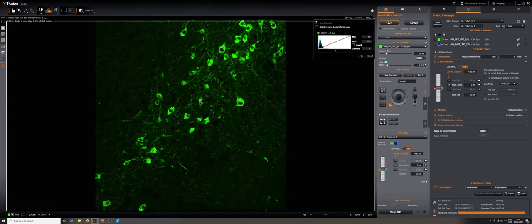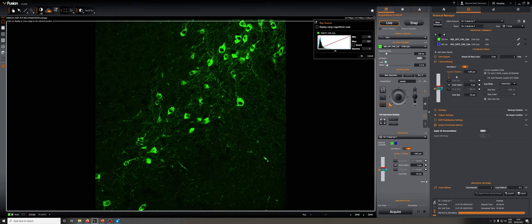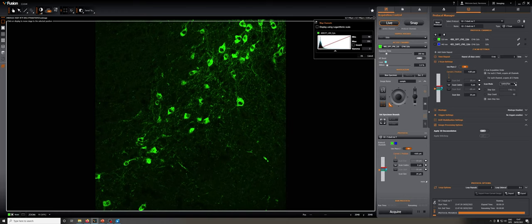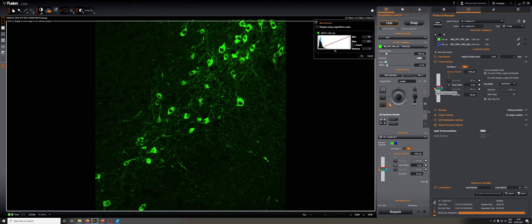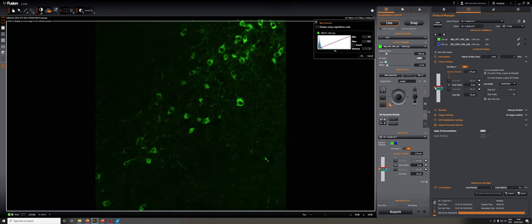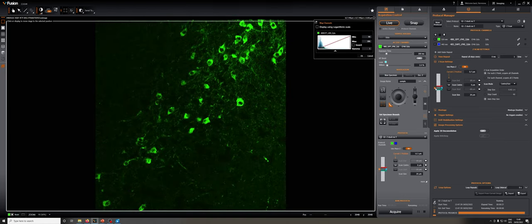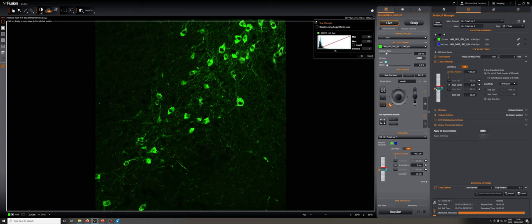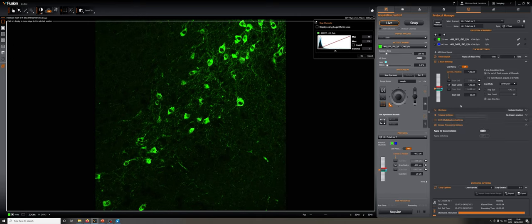So how do we set up a Z stack? There are several ways of doing this. We always want the use piezo engaged. The two ways of doing this are to use center and size or start or end. In center and size, what we do is set a given position as the center. We move the piezo until we find where we think the center is, there, and then we set that as the center of our Z stack.